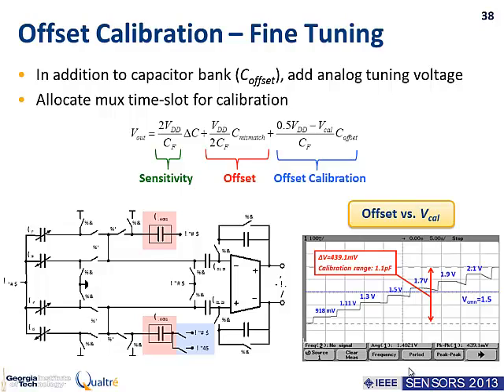The reason this is advantageous is because usually getting finer steps in voltage is a lot easier than getting fine steps in capacitance. Here's an example of a calibration done on an accelerometer by changing the calibration voltage.